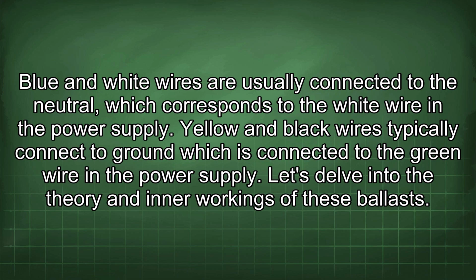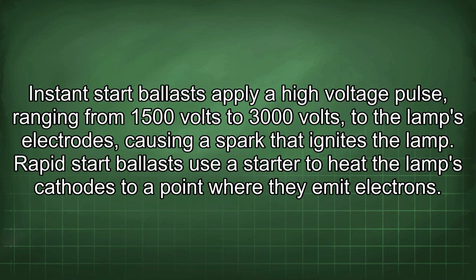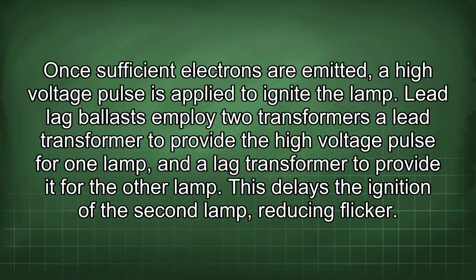Let's delve into the theory and inner workings of these ballasts. Instant start ballasts apply a high voltage pulse, ranging from 1500 volts to 3000 volts, to the lamp's electrodes, causing a spark that ignites the lamp. Rapid start ballasts use a starter to heat the lamp's cathodes to a point where they emit electrons. Once sufficient electrons are emitted, a high voltage pulse is applied to ignite the lamp. Lead lag ballasts employ two transformers, a lead transformer to provide the high voltage pulse for one lamp, and a lag transformer to provide it for the other lamp. This delays the ignition of the second lamp, reducing flicker.